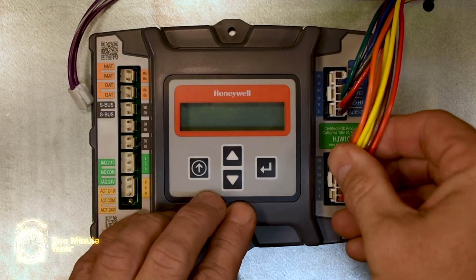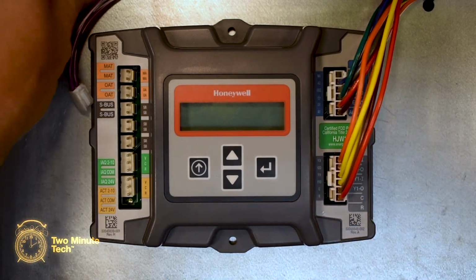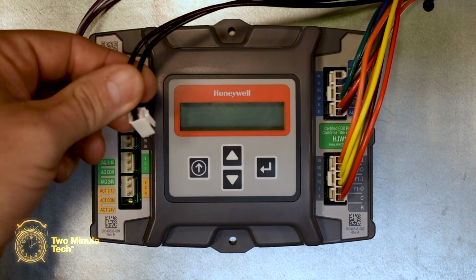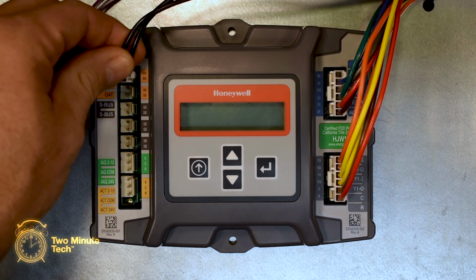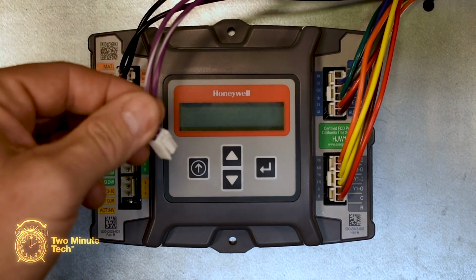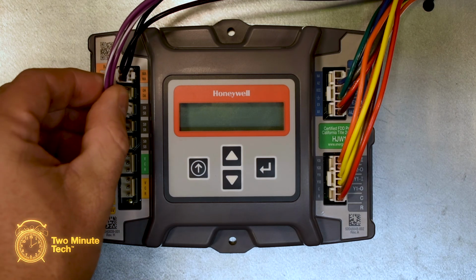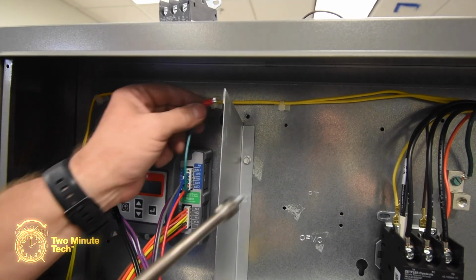The 6-pin plug with the 2 orange, 2 yellow, brown, and red wires connects to the connector marked with gray on the lower right side. The 2-pin plug with the black wires connects to the connector marked with orange and MAT at the upper left side of the controller. The 2-pin plug with the purple wires connects to the connector marked with black and S-bus. The green ground wire with the ring terminal gets connected at the back of the control box with the provided screw.